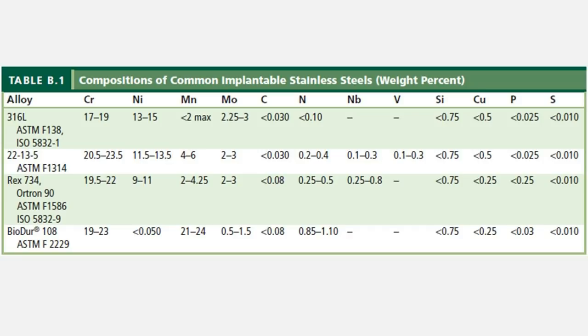Now, the reason why this came about is that nickel itself can impart a lot of hypersensitivity reactions, even some cytotoxicity reactions, whenever the stainless steel, despite its name, eventually does corrode, and at this point we're thinking long time scales like 10-year implants, nickel and other trace elements get released through that corrosion process. And nickel has some adverse events in the body, and we've really just started noticing that in the past few decades as people and patients with long-term implants have realized the long-term effects of nickel. Despite that, the 316 alloy is still commonly used, especially in acute applications, in part because it's so easy to manufacture, it's cheap, and it just has a long history in use in biomaterials.